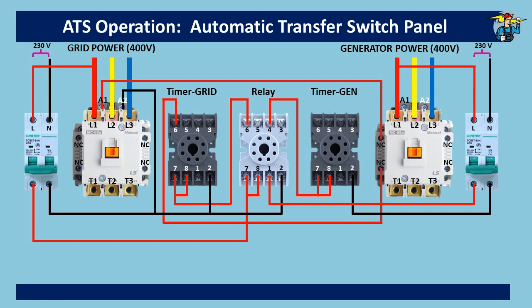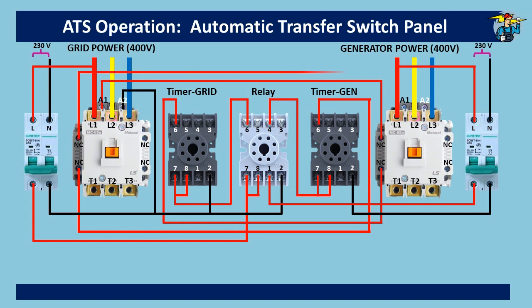Power from port 7 is connected to common port 8 of the generator timer. The generator timer outlet port 6 is normally open but closes and connects with inlet port 8 after the set time delay. Port 6 of the generator timer is then connected to A1 of the generator contactor, also going through the normally closed auxiliary contact of the grid power contactor for interlocking safety. Neutral wire connects to A2 of the generator contactor to complete the generator side control circuit.